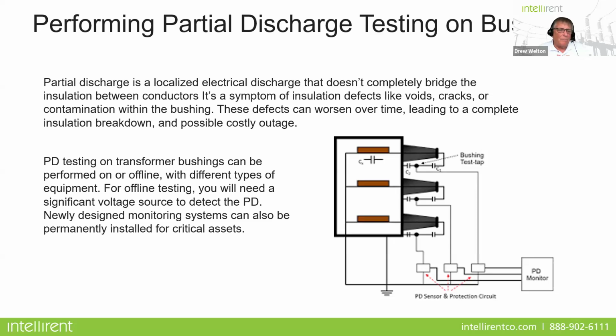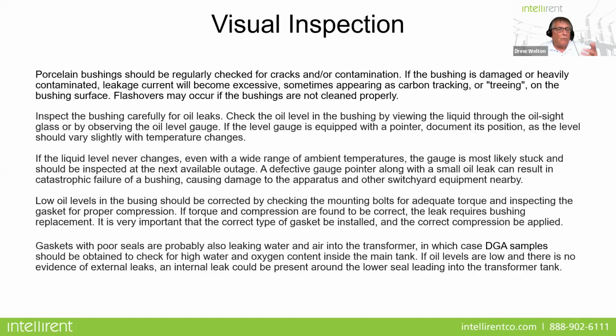For PD measurements on transformer bushings, the good news is you can do it either online or offline. If you're doing it offline, of course, you need a voltage source to energize the bushings, which can sometimes be a little bit difficult. So again, visual inspections: look at the porcelain for cracks or contamination, look for oil leaks. If your oil level never changes, even with a wide range of ambient temperature, there's a pretty good chance your gauge is stuck. So look for that as well.